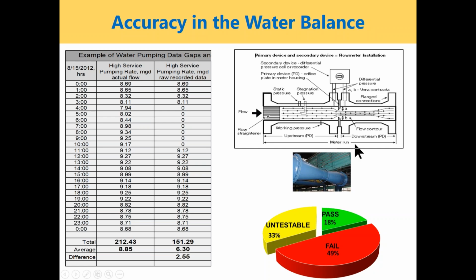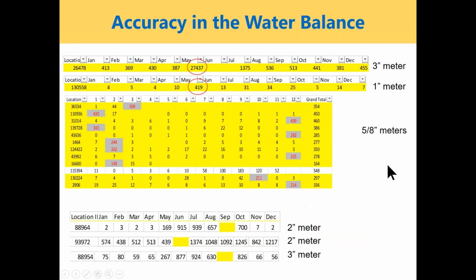That last example I mentioned about the meter being too close to the check valve, that was one of many tests conducted in the state of Georgia. They did some state-funded assistance, and what they found was a high rate of failure of those meter setups, almost half, and then another third were not testable because the plumbing was so tight there was no place to get on to conduct a secondary meter and run a test. So this is super problematic in how wide and extensive these types of issues can be. That's a big deal.